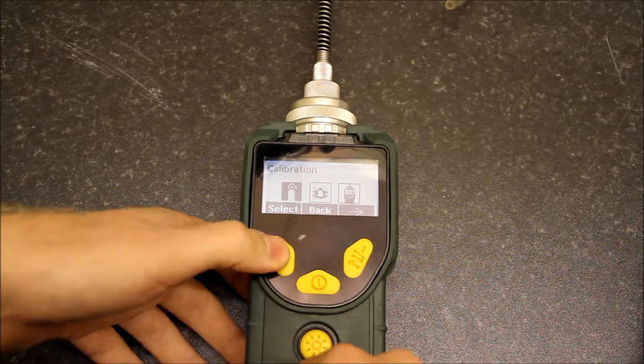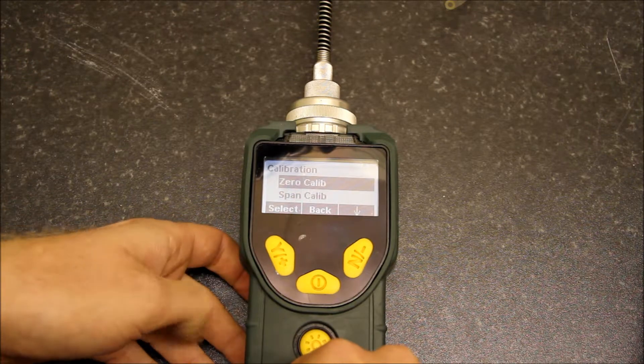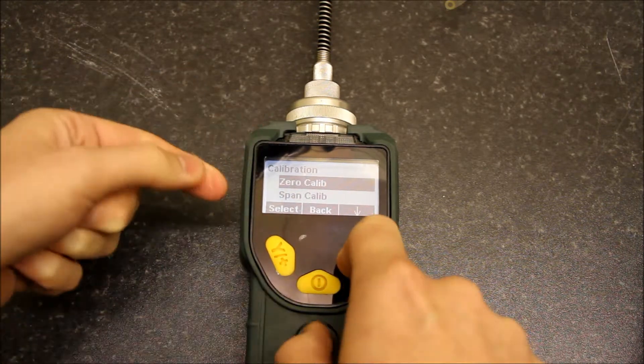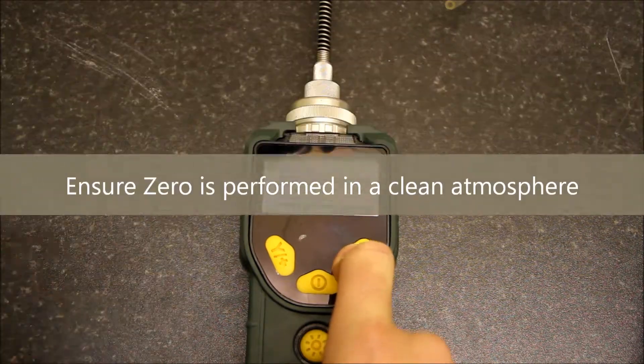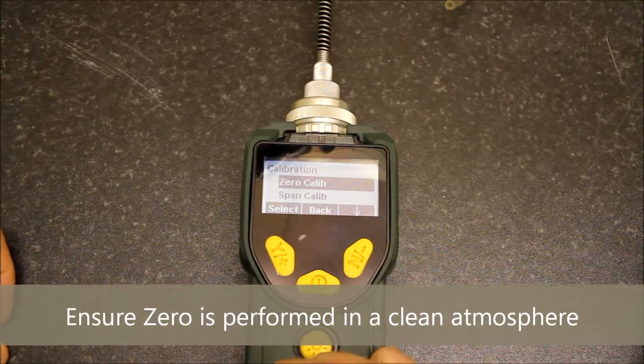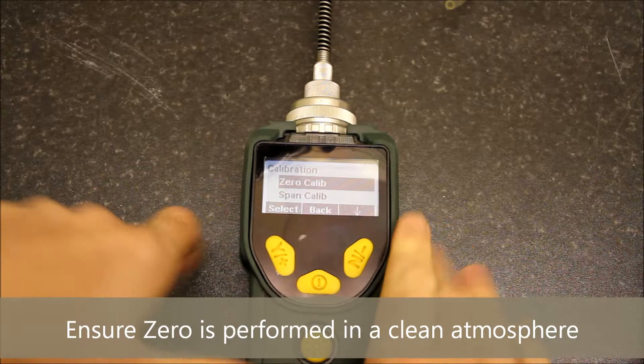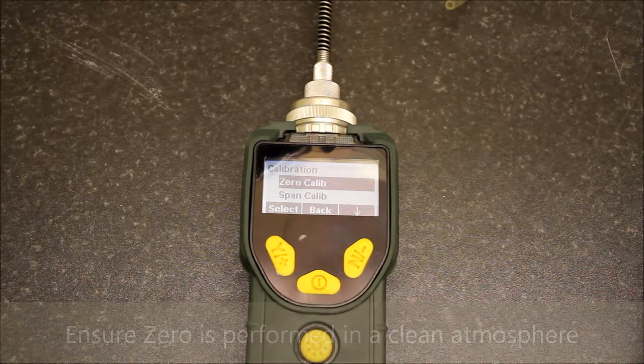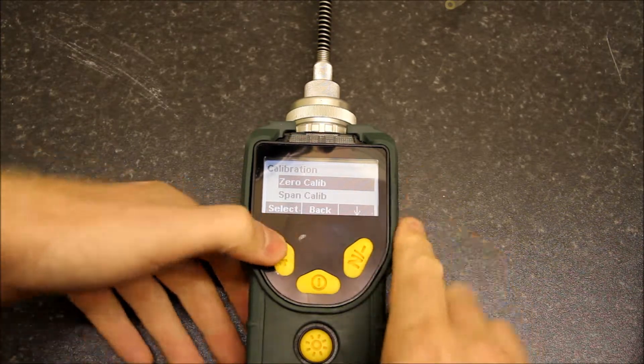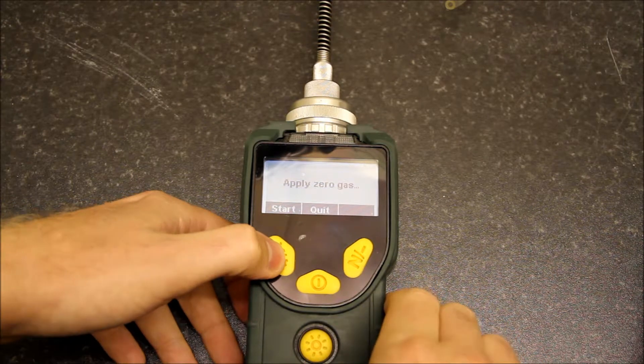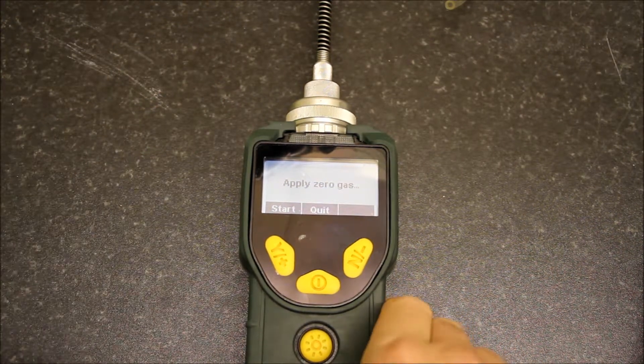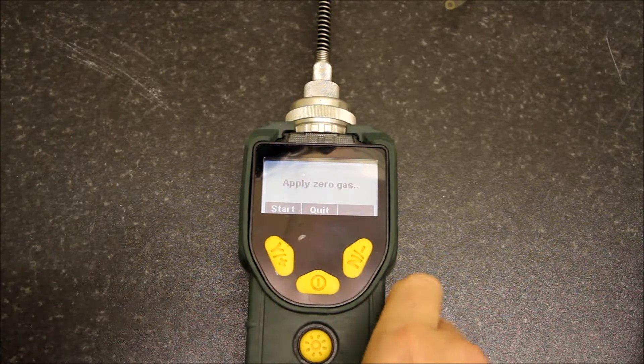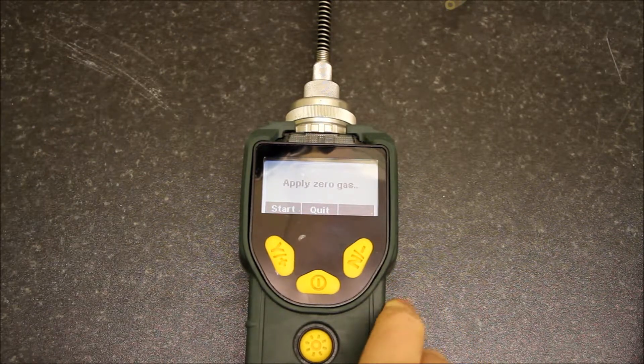Under the calibration menu, we've got zero calibration, span calibration, and bump. We're going to do a quick zero calibration. My monitor has been running for 15 minutes, which has allowed all the electronics to warm up. If I select zero calibration, it's asking for zero gas. Ideally we need to be in an atmosphere with no contaminants of VOC.